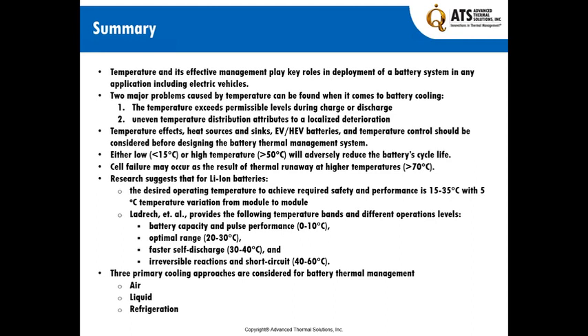Research suggests that for lithium-ion batteries, the desired operating temperature to achieve required safety and performance is between 15 to 35 degrees C, with 5 degrees C temperature variation from module to module. A daunting task - it's not easy to attain, especially if we don't have the proper resources to design a cooling system that fits the application.